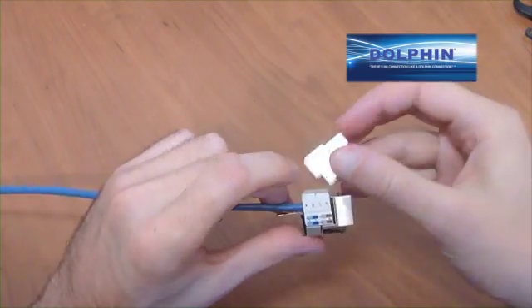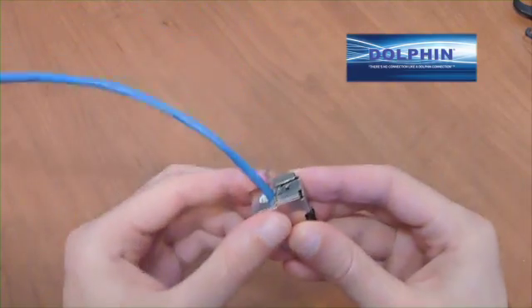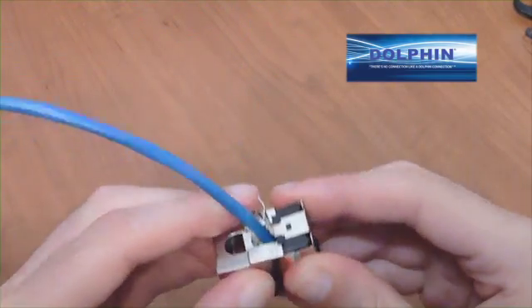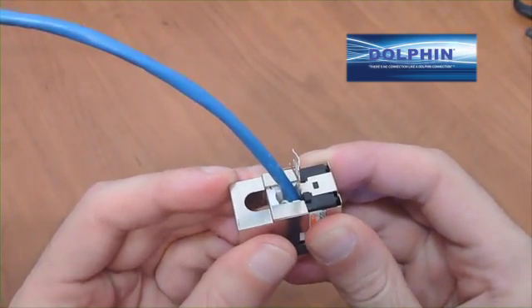Use a 5E or 6 connection tester to certify the connection and remember, to ensure that you maintain your cable rating, make sure that the outer cable insulation is inserted into the entry tunnel of the strain relief cap.